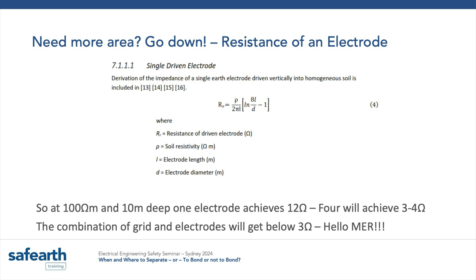That formula there, again, pretty simple: resistivity on 2 pi L multiplied by a little logarithmic formula. In 100 ohm meters, a 10 metre deep electrode will get you 12 ohms. If you put 4 in each of the corners, you'll get down to around 3 to 4 ohms. If you combine this little new system with the previous system, you'll get down to just below 3 ohms.